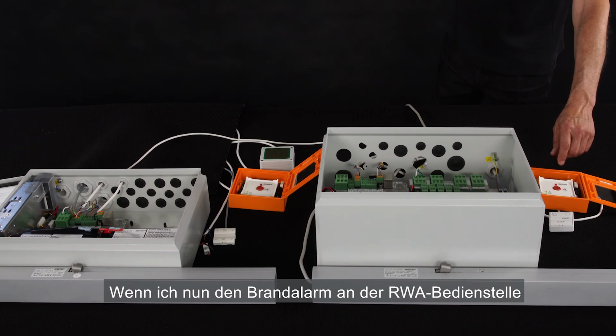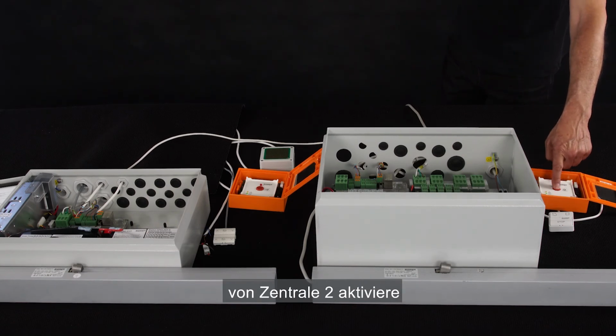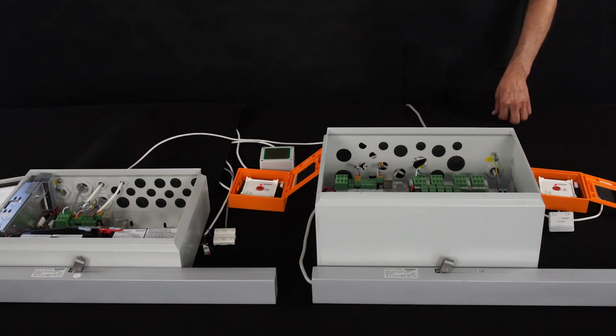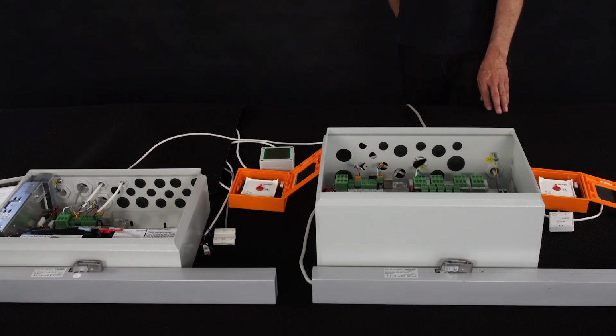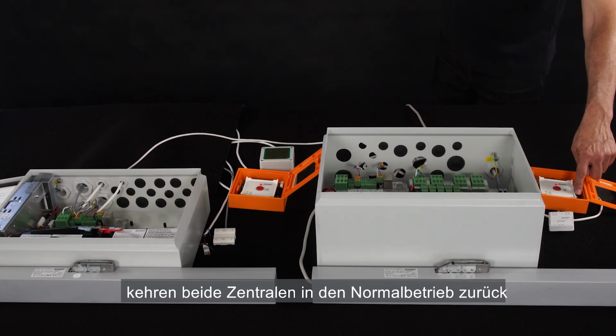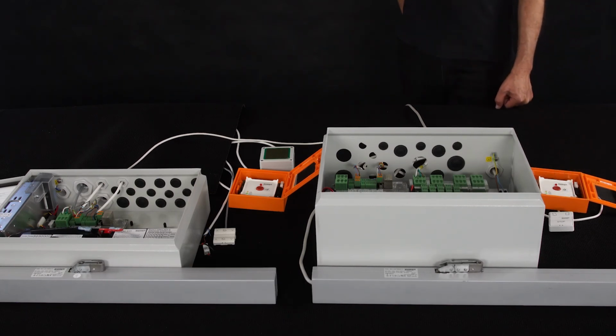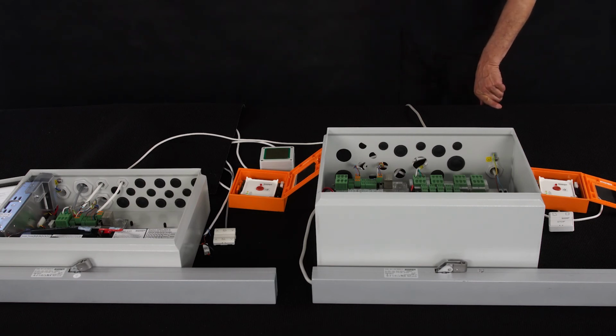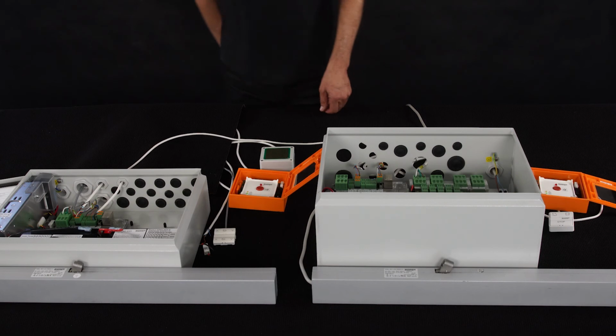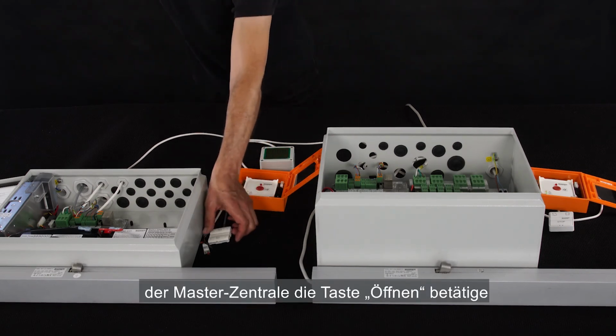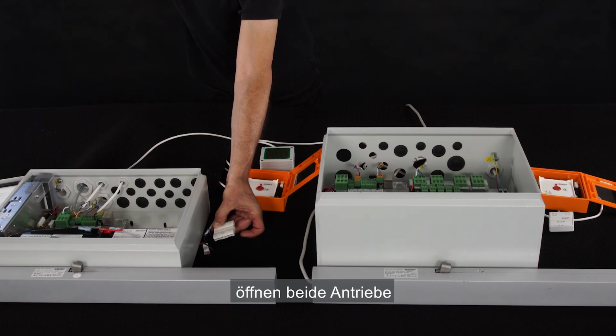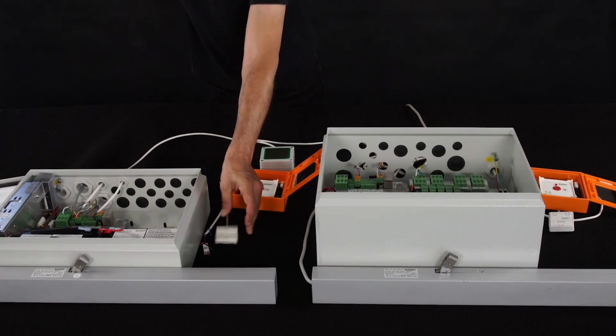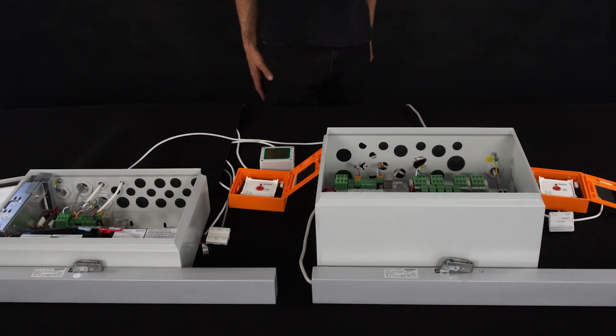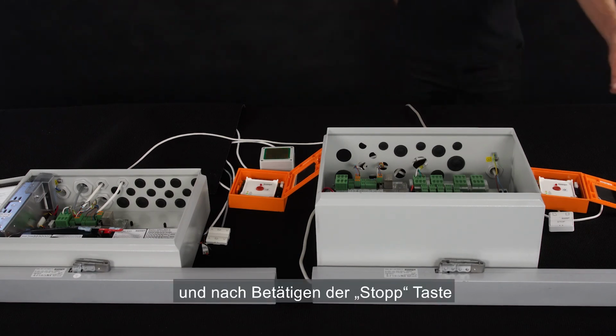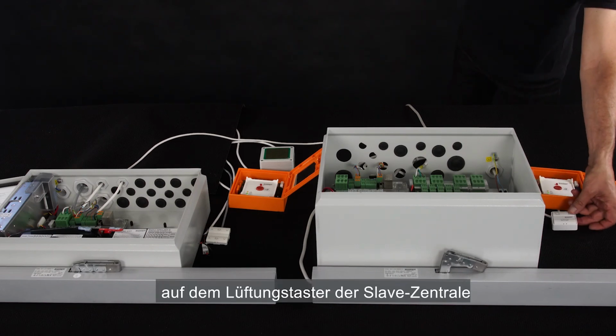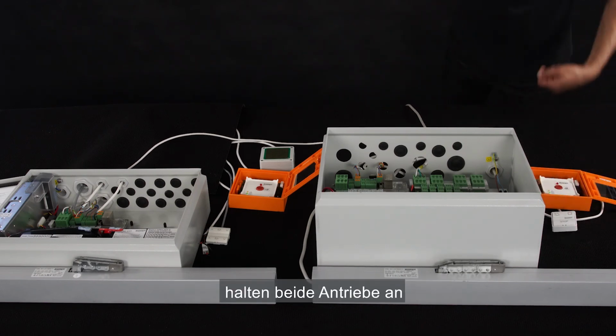If I move to panel 2 and activate the fire alarm from the break glass unit, both panels react. I reset and both panels go to normal operation. If I press the open button on the switch connected to the master panel, both actuators open. And if I close using the stop button on the switch connected to the slave panel, both actuators stop.